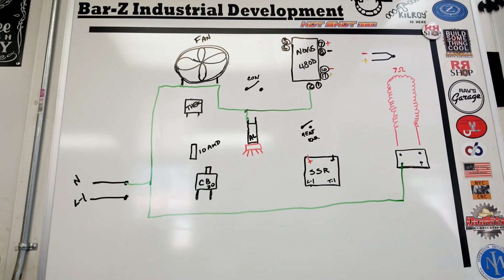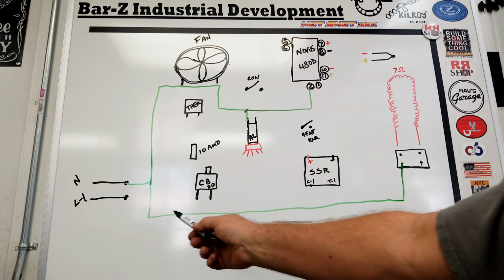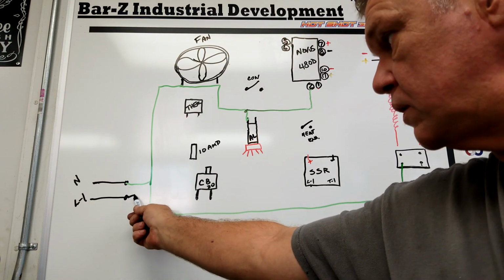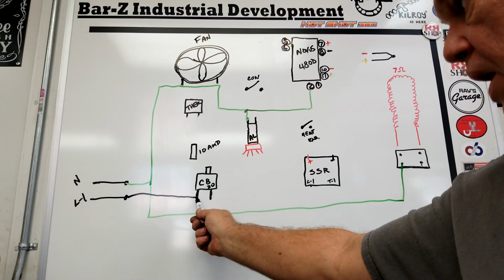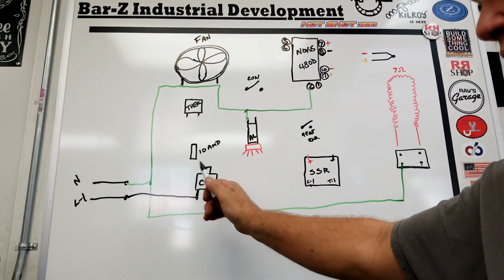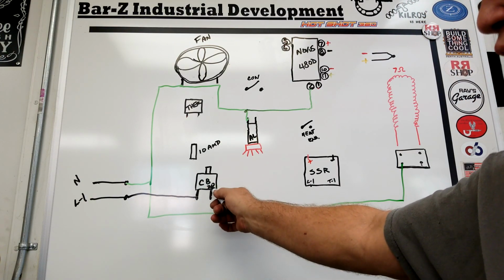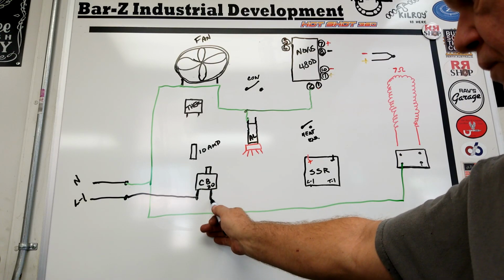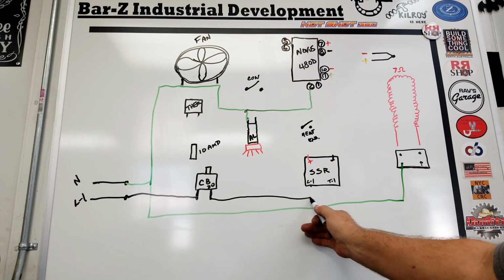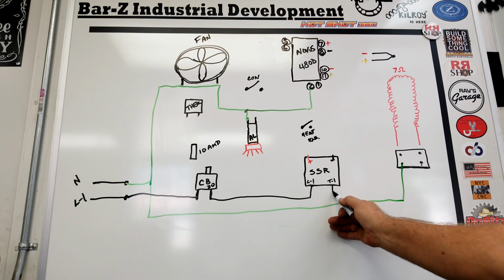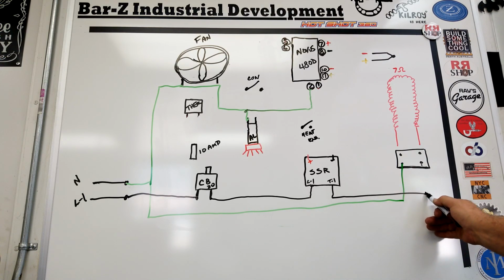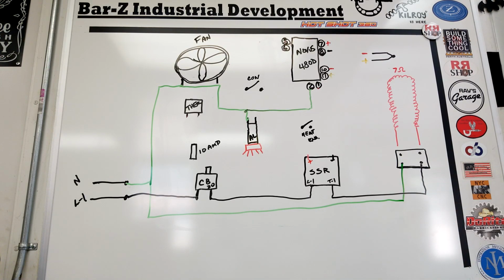Next up, we're going to take power. And I'm going to use the colors that I actually use within the unit. So we bring incoming power in. I do that in black. That's black on the power cord. We hit that circuit breaker first thing. That's a 20 amp circuit breaker that I showed you earlier. And then we come out of there. We go to the SSR. Out of the SSR, right into our terminal block. Okay.